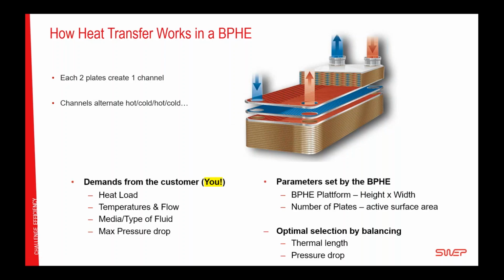So the information we need from you, dear customer, is how much energy do we need to transfer? What are the temperatures and flows? What kind of fluid or media are you planning to use? And what is the maximum pressure drop that you can allow when the fluid goes in, through, and out, right? And with the data that you give us, we can choose the BPHE platform, everything from the B3, the palm size, to the 4-feet monster. So that sets the height and width of the heat exchanger, and then we start to add plates from the minimum of 4 plates up to the maximum of 400 something, and so then we have the size and the heat transfer area.